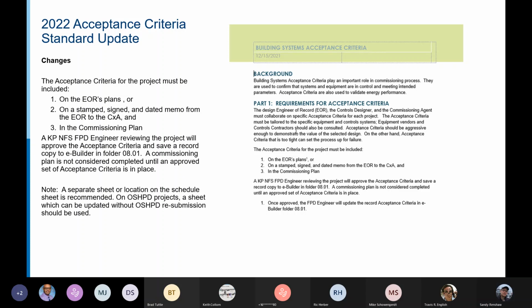So the changes here, and I'll just read through them. The acceptance criteria, traditionally the engineer of record has put that into the BOD, and that's probably good for the beginning to start talking about it. But we want the acceptance criteria as part of the contract documents, which means we want them on the engineer of record's plans. You could also do it in a specification section. And finally, you could do a stamped and signed dated memo from the engineer of record to the commissioning agent.